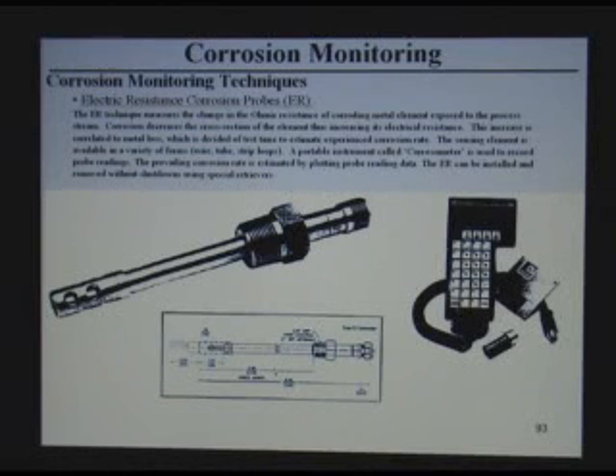There is a portable corrosometer that hooks up to the ends of the wires and measures the resistance. Each time you make a measurement, you plot it on a curve, and from that curve there's a formula you can use to calculate the corrosion rate. If it's high, you find out why and make changes in the process.